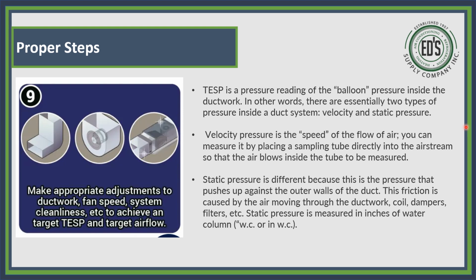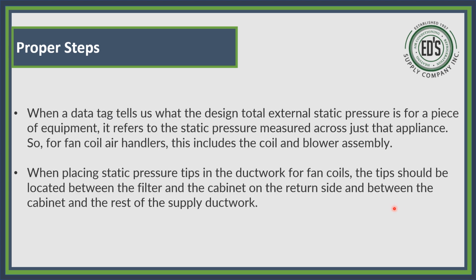Static pressure is different because it is the pressure that pushes up against the outer walls of the ductwork. This friction is caused by air moving through the ductwork. Remember I said the friction rate is that we usually size our ductwork at 0.1 friction rate. That's what this is. Then you have coils, dampers, filters, etc. Static pressure is measured in inches of water column. Now, when a data tag tells us what the design total external static pressure is for a piece of equipment, it refers to the static pressure measured across just that appliance. So for the fan coil or air handlers, this includes the coil and blower assembly. Nothing else, not the return boxes, not the return filters, none of that. All that's considered extra or an accessory.